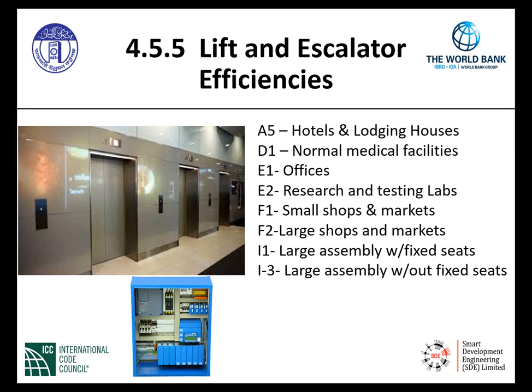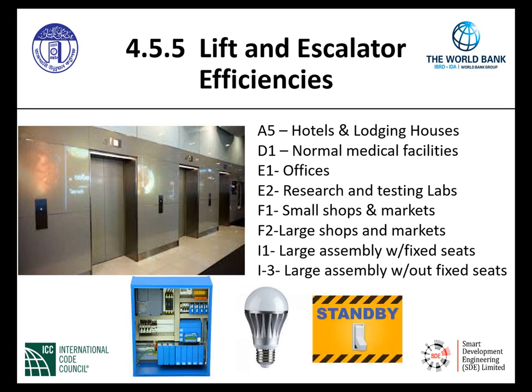It takes a lot of energy if you think about it. So you have this lift, and it takes a lot of energy to get it going and a lot of energy to stop it, that braking horsepower to stop it. And so anything that you can do to cut down on that energy consumption, and these VVVF drives do that. So it's telling you you need to use those. And it also says on elevators, high efficient lamps with provisions for switching off when the lift is inactive for a period of up to 5 minutes. And then the provisions to operate in standby condition during off-peak periods when the lift has been inactive for at least 5 minutes. So again, we're going to see how all of this ties in later on with some other provisions in the code.